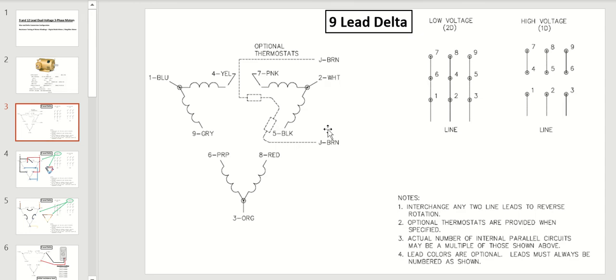What you need is this type of information here, and if it's a 9-lead delta motor, this is the configuration that you would see for connecting it with a low voltage, which is typically 208 to 230 volt, or high voltage, which is typically 460 to 480 volt. Here it shows optional thermostats. If you have a safety circuit, that would be an option that you could purchase with that particular motor.